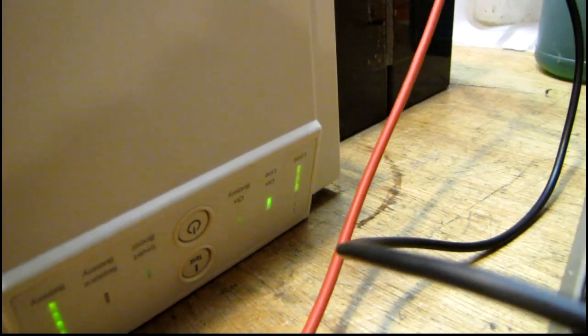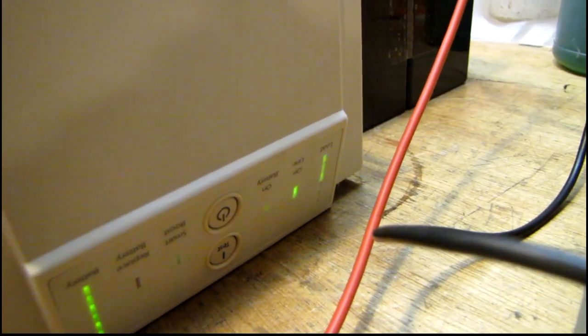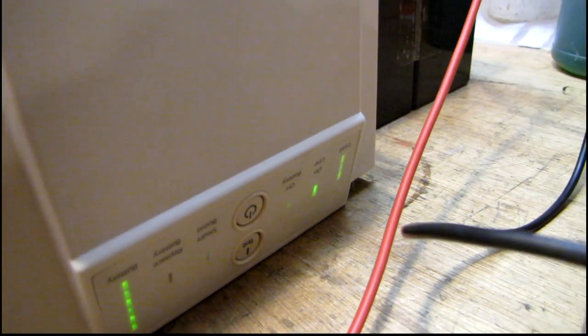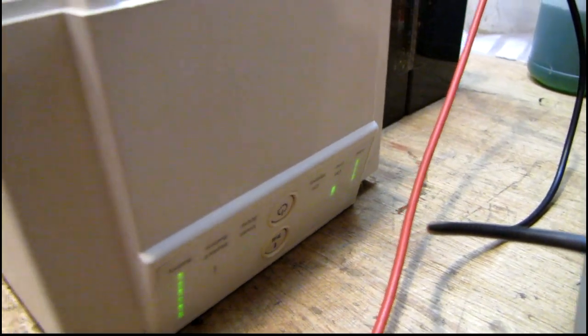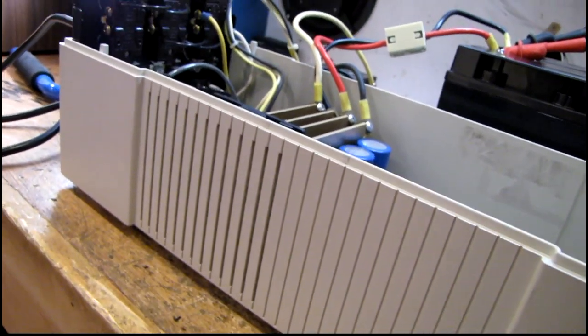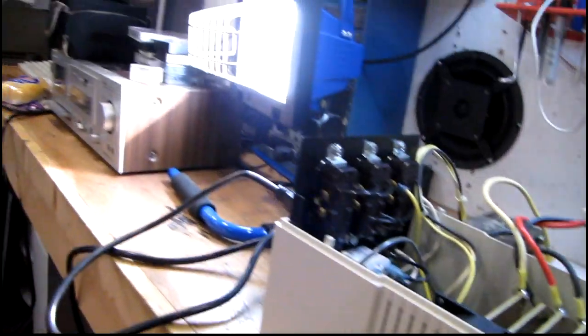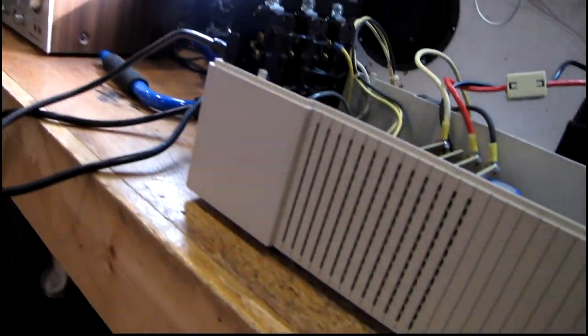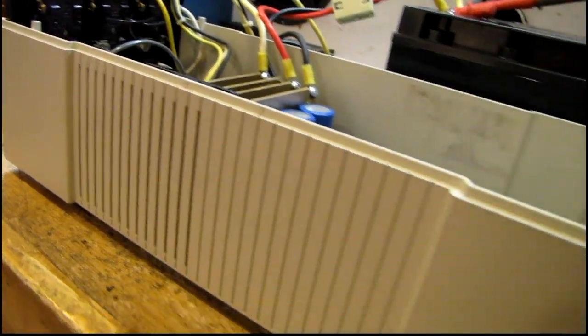We're running about 50 to 60%, should be a little over 50% actually. Got 3 out of the 6 load indicators lit. This is a 950 watt UPS and it's got a 500 watt load connected, so right about ideal.